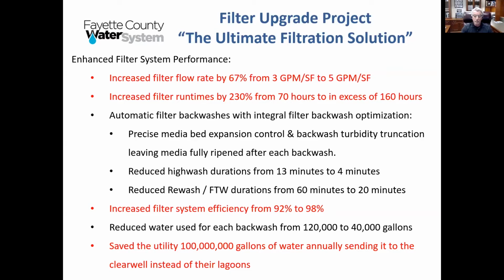But all this water added up to a savings from using 120,000 gallons of water to only needing 40,000 gallons of water to do a backwash at this point. And that actually accumulated over a year annually to up to 100 million gallons of water. Now, 100 million gallons of water that this plant was wasting prior to the project every year, translated at 6.8 mgd, which was their average flow rate, to 14.75 days of production being sent to lagoons instead of their clear wells for no reason other than poor operational procedures and poor technology.